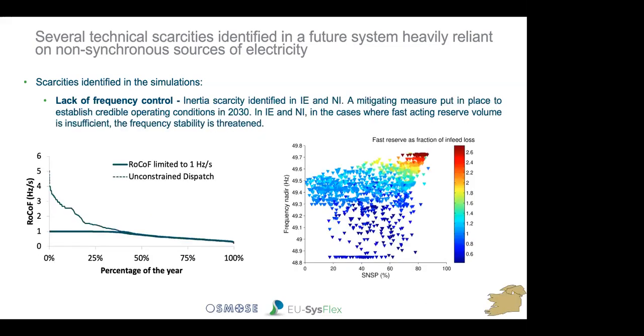On the next slide, I've introduced work conducted for the frequency analysis of the Ireland and Northern Ireland power system. It was found that without significant mitigations, there will be significant inertia scarcities in 2030, and therefore challenges with high rates of change of frequency. In some cases these rates were so high that they needed to be limited in the generation dispatch itself to create credible dispatches for future analysis, and this mitigation is an option we also explored as a solution in further studies.